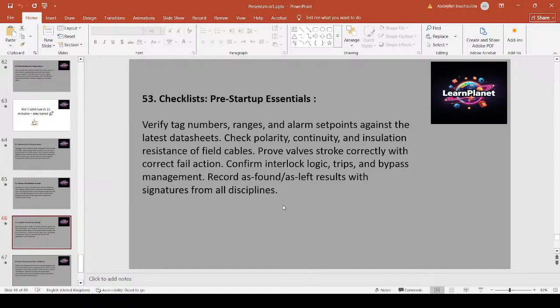Checklist, pre-startup essentials. Verify tag numbers, ranges, and alarm set points against the latest datasheet. Check polarity, continuity, and insulation resistance of field cables. Prove valve stroke correctly with correct fail action. Confirm interlock logic, trips, and bypass management. Record as-found, as-left results with signature from all disciplines.